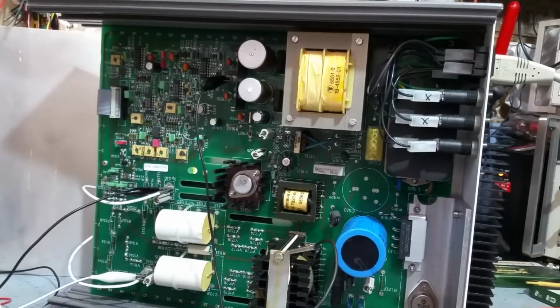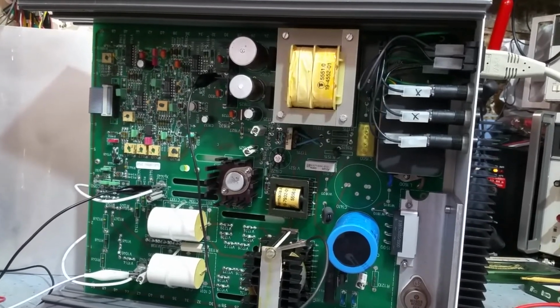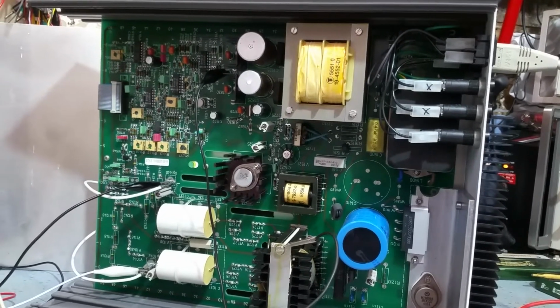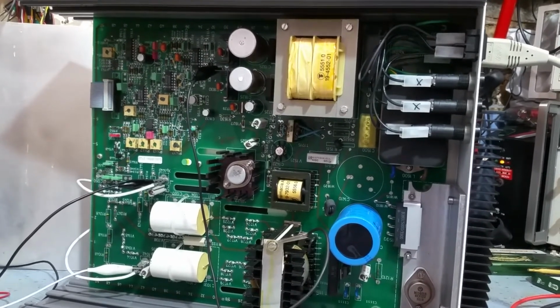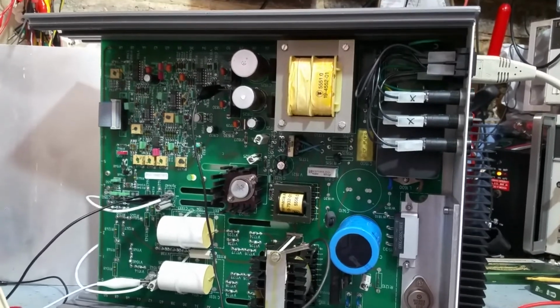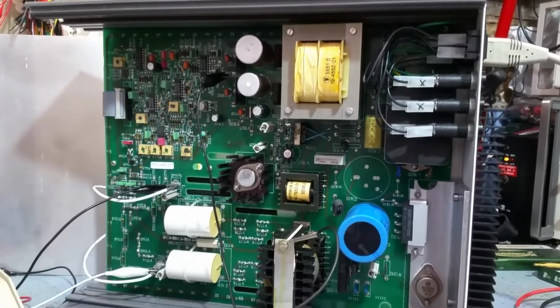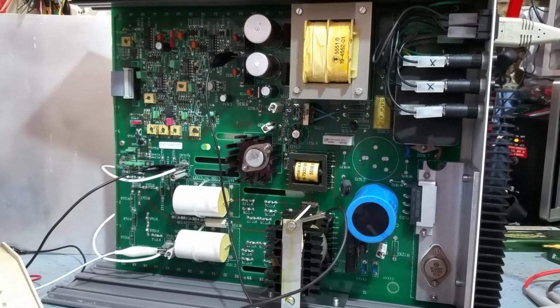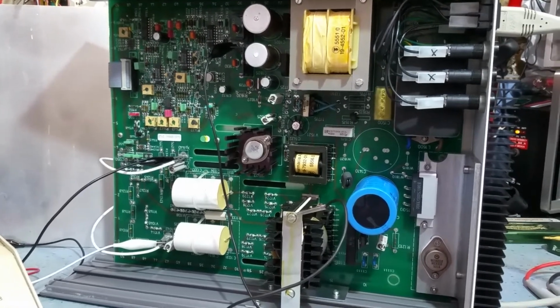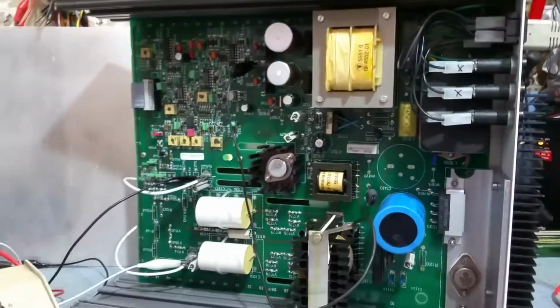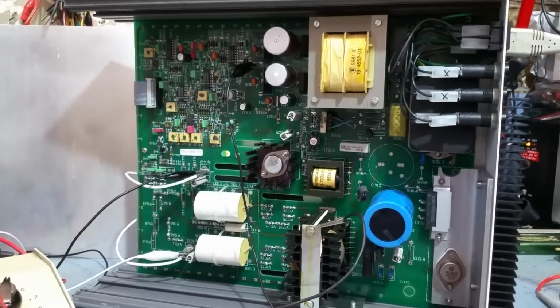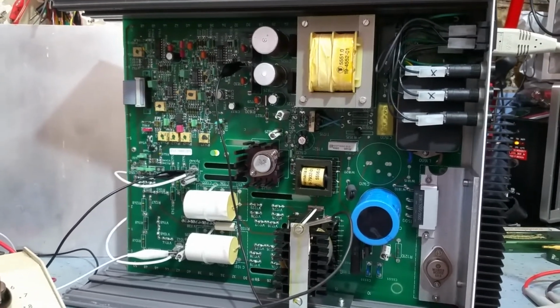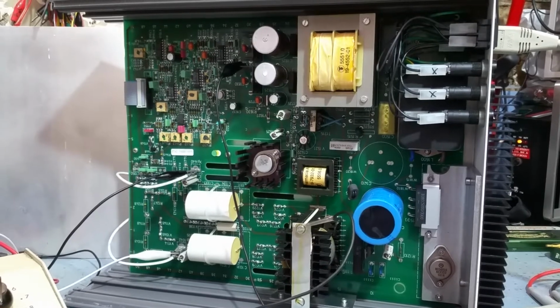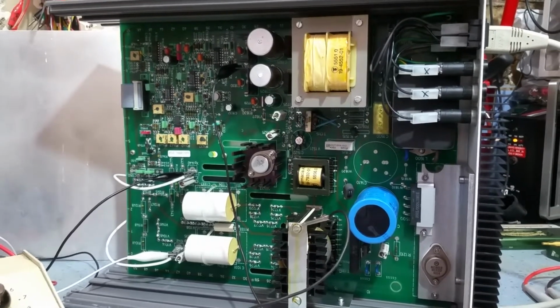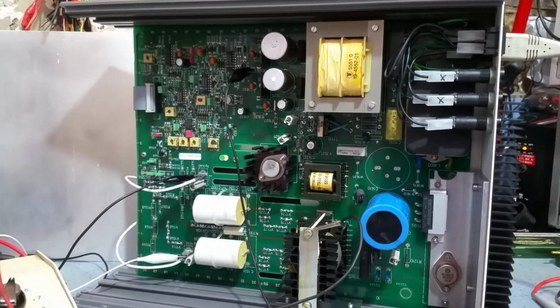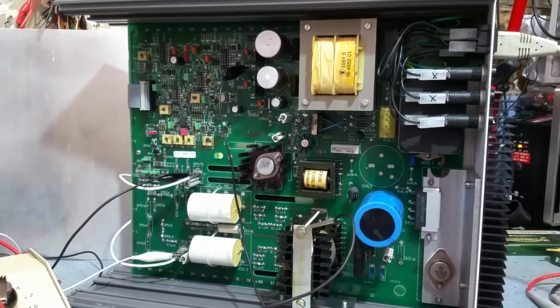So today is the day I've been looking at it. The unit had two problems that make it more or less unusable on the bench for anything other than maybe the pharmacy market, and I don't even know if this one's got a fault - I'm not sure it's supposed to do this. There's no information at all on these. It's a highly dangerous piece of equipment, actually - something that produces 3 kV at 150 milliamps will fry you. It's a really nasty bit of kit in the wrong hands.